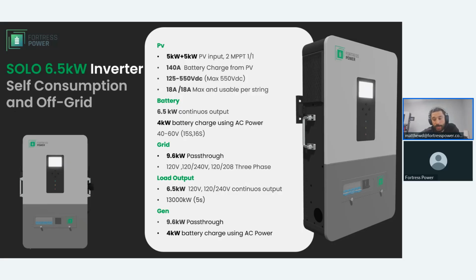The battery can charge and discharge continuously at 6.5 kilowatts, and hence why the inverter has that rating of 6.5 kilowatts, where 4 kW can be charged using AC power, okay? Maximum of 4 kW using AC power. That's either grid or generator. It is applicable to use with 15-cell and 16-cell batteries. And the reason why I say that is because we do have a 15-cell battery called the eForce, which could be well suited for this type of application. But we highly recommend using the 16-cell eBoost, just because it is a more cost-effective solution when paired with this inverter, right?